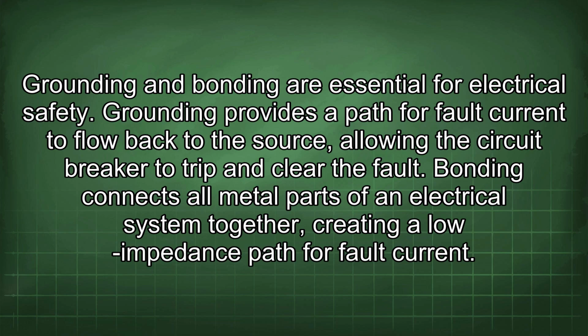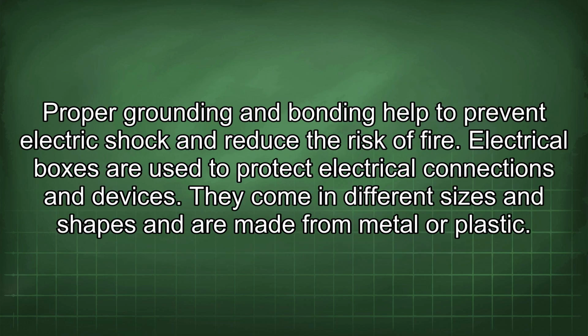Grounding and bonding are essential for electrical safety. Grounding provides a path for fault current to flow back to the source, allowing the circuit breaker to trip and clear the fault. Bonding connects all metal parts of an electrical system together, creating a low impedance path for fault current. Proper grounding and bonding help to prevent electric shock and reduce the risk of fire.